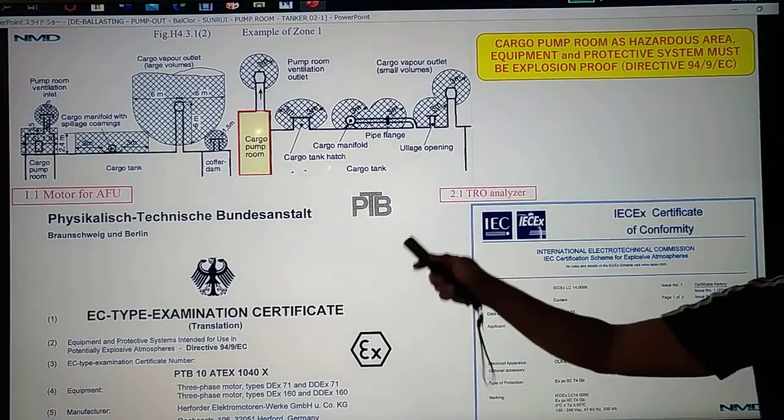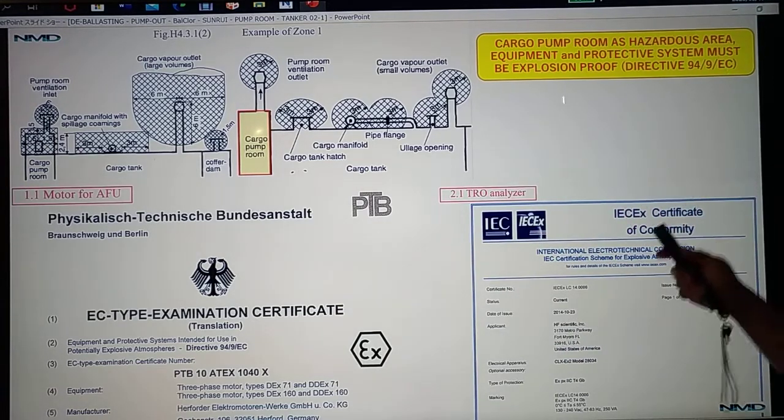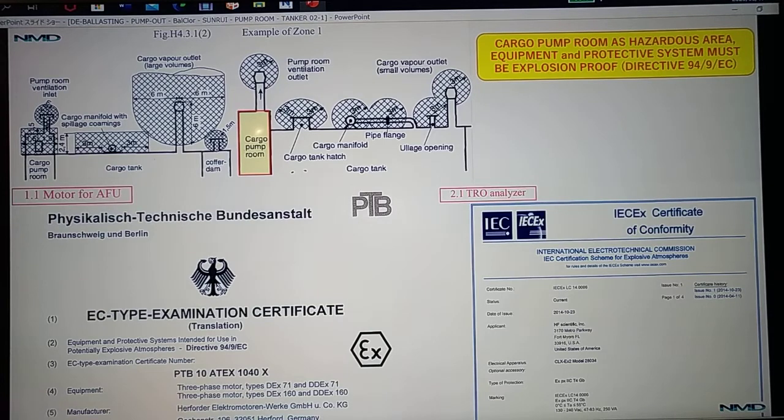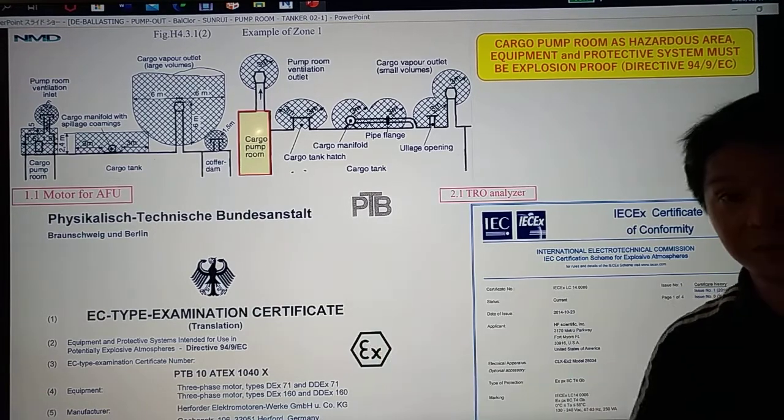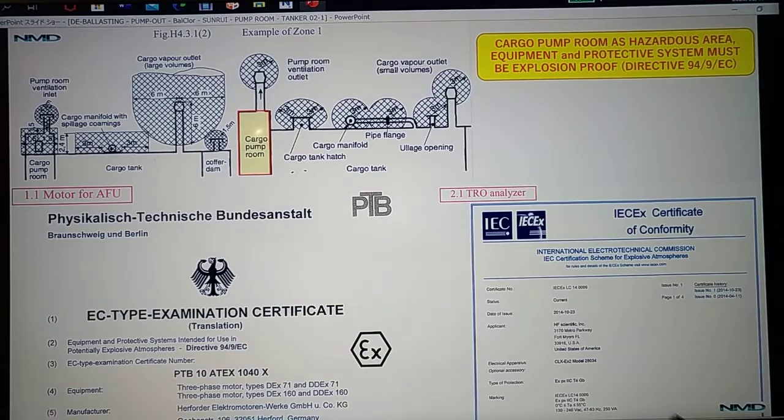Our cargo pump room, as a hazardous area, requires that equipment and protective systems must be explosion proof. Check from your maker that you have the certificate confirming that the AFU and TRO analyzer are explosion proof.